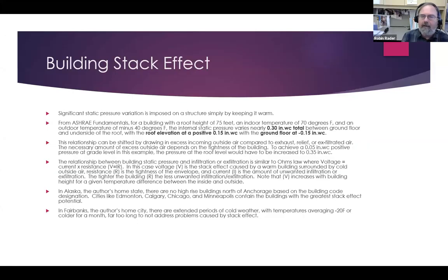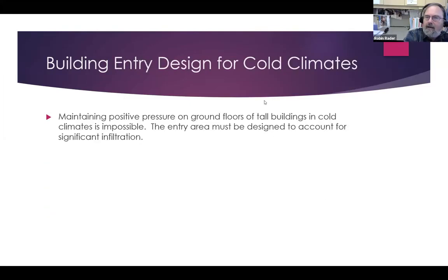However, in Fairbanks, there are extended periods of cold weather with low average temperatures for months at a time. So that's far too long to not address the problems caused by stack effect. Maintaining positive pressure on the ground floor of tall buildings in cold climates is impossible. At least that's the conclusion we've come to. The entry area must be designed to account for significant infiltration.